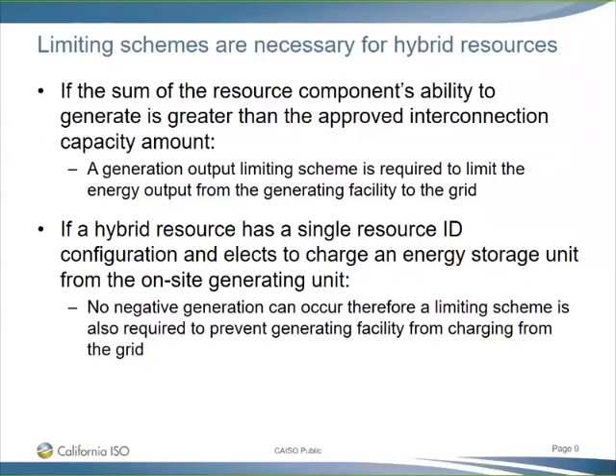The next point is that hybrid resource IDs under a single resource ID configuration that elect to charge the storage component from the on-site generating unit can't have any charging from the grid. In other words, no negative generation can occur, and therefore a limiting scheme is also required to prevent those facilities from charging from the grid, so that there's no negative generation to the grid to charge that resource.